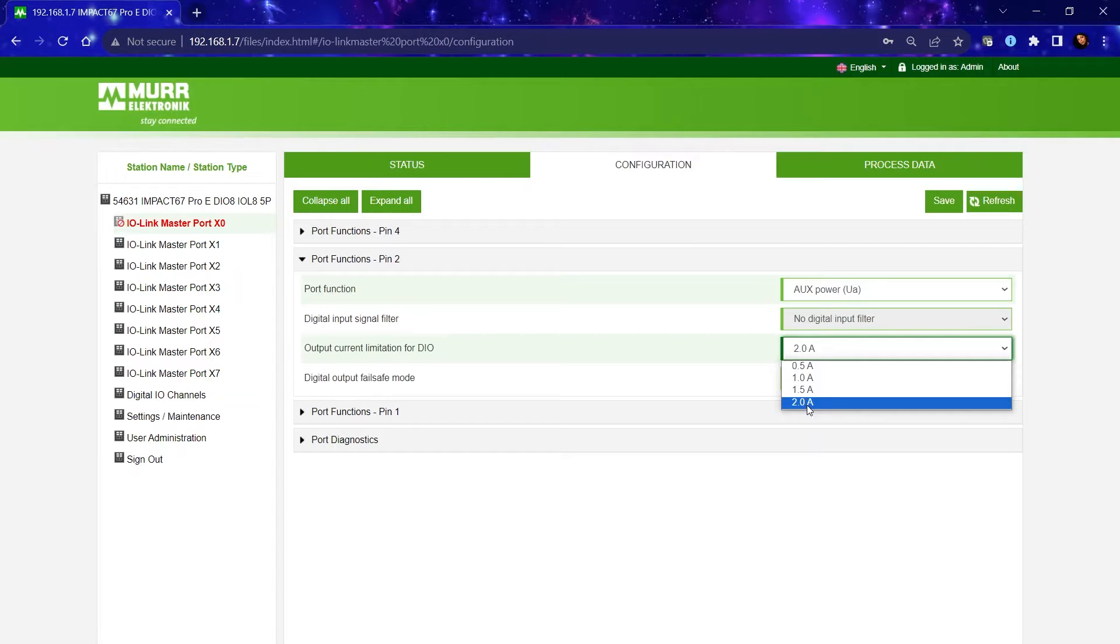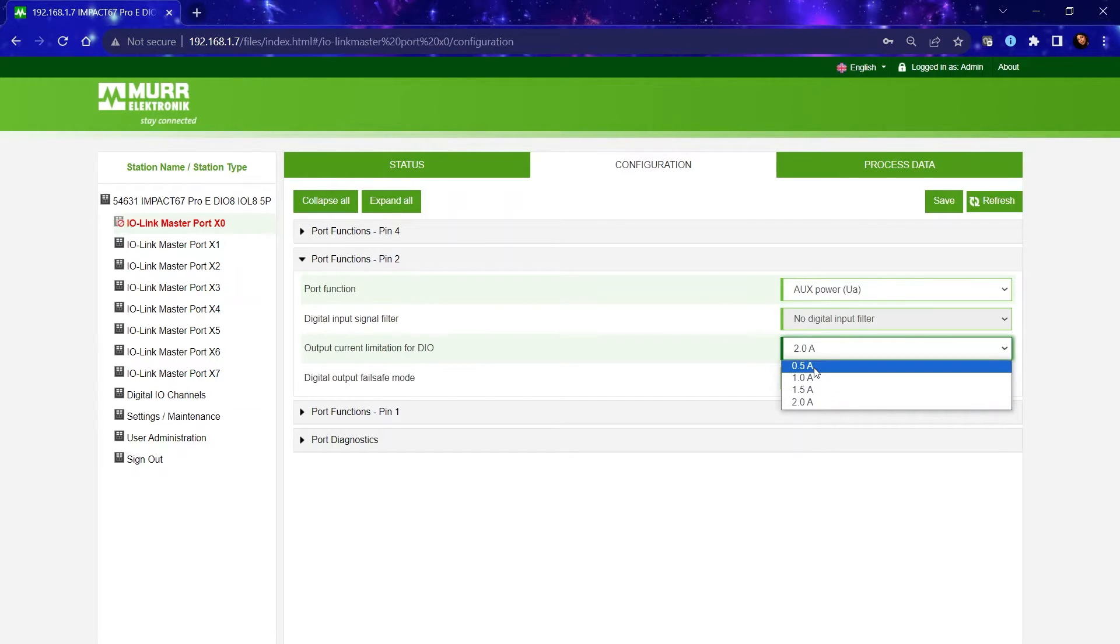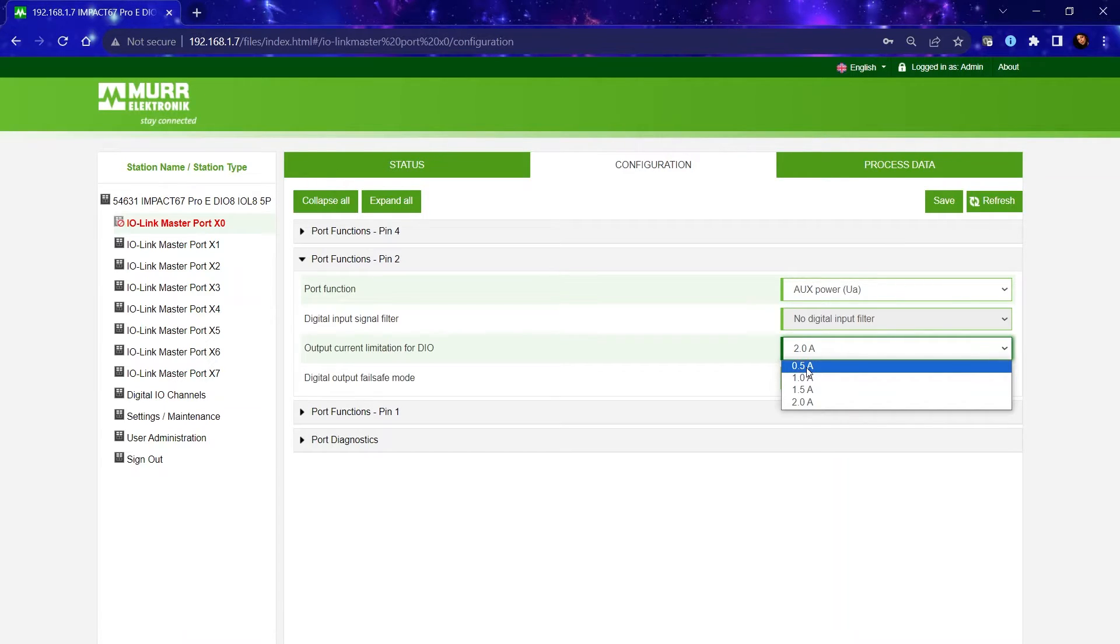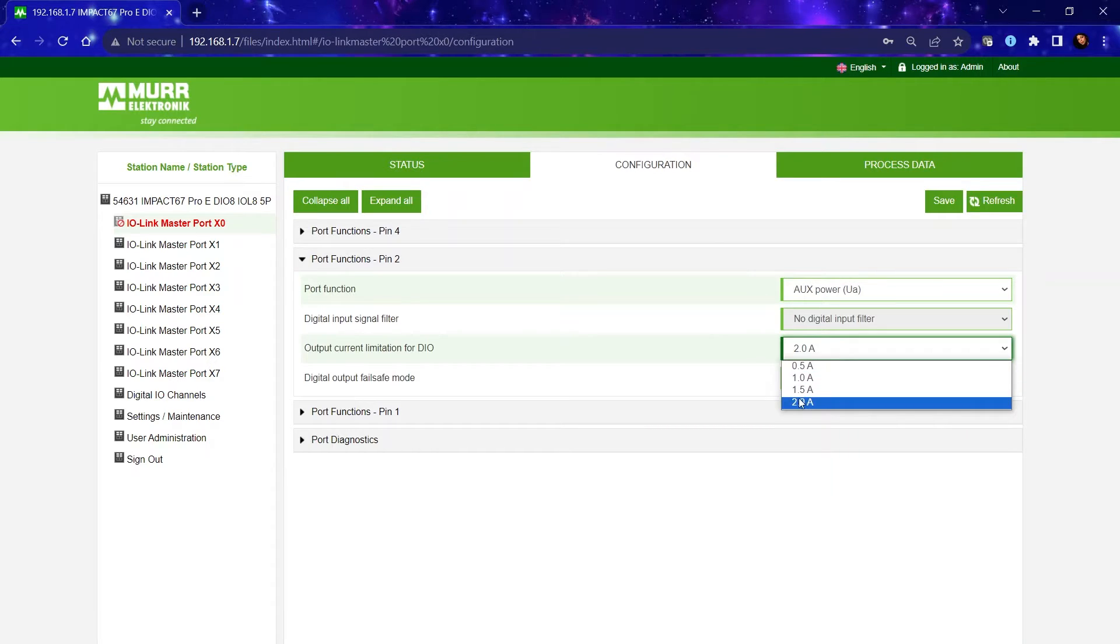So for example, if you were to connect a sensor that only takes 100 milliamps, you would want to set the output current to half an amp. So if a short circuit was to occur at half an amp, it will most certainly show that diagnostic message in a much shorter time than if you have it as a 2 amp setting.